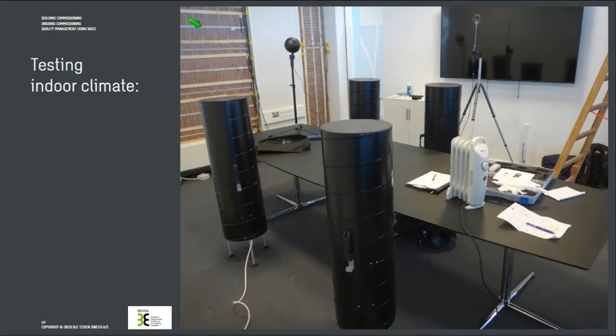And here you have the window that's covered with a piece of chipboard. This is actually floor heating cords spread out here to assure that the heat load coming into the room during the test is the same as we measured coming in real life from the window.